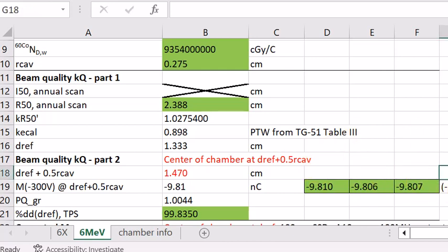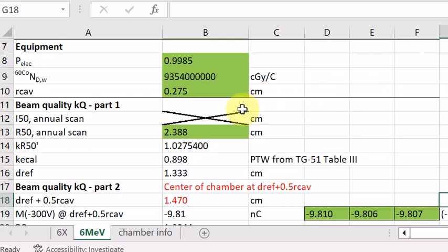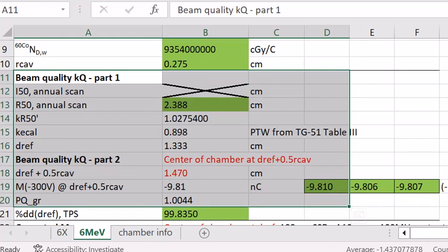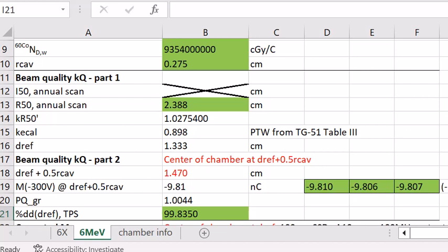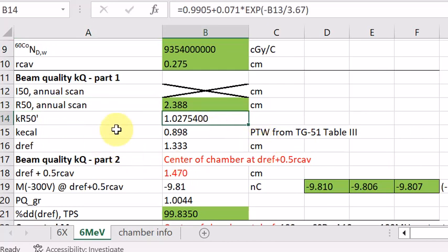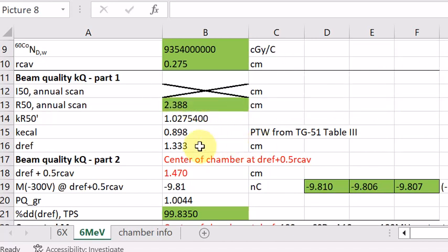How do we find the KQ factor for the 6 MEV electron beam? We need the chamber information, specifically the radius of the cavity, because we need it for the P gradient factor. We use a cylindrical chamber for our TG51, so our P gradient is not equal to 1. For the beam quality, we first scan the PDD and find the R50 value from our annual scan. In this case, R50 is 2.388 cm for the 6 MEV electron beam, and we immediately find the KR50' factor using the equation from TG51.